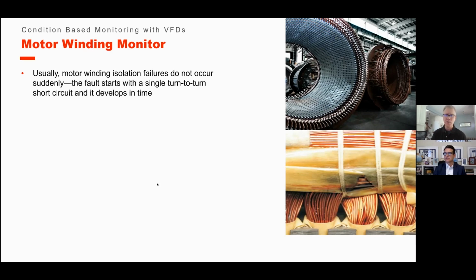And drives, VFDs, are notorious for sending out high voltage spikes at very high frequencies. So you get a lot of problems and breakdown in the first 3 turns of a coil going into a motor. You'll see a picture of that. What you're looking at there is a turn-to-turn short developing. And that develops over time. As it starts to degrade, you can actually still run that motor. You'll have signs, but that motor will still run until the point of total failure.